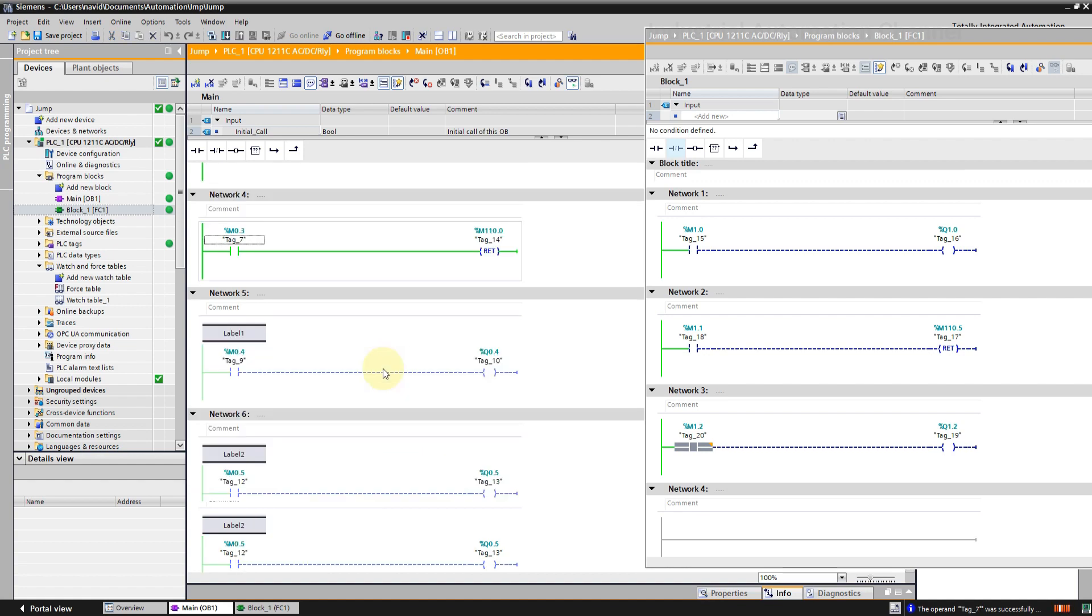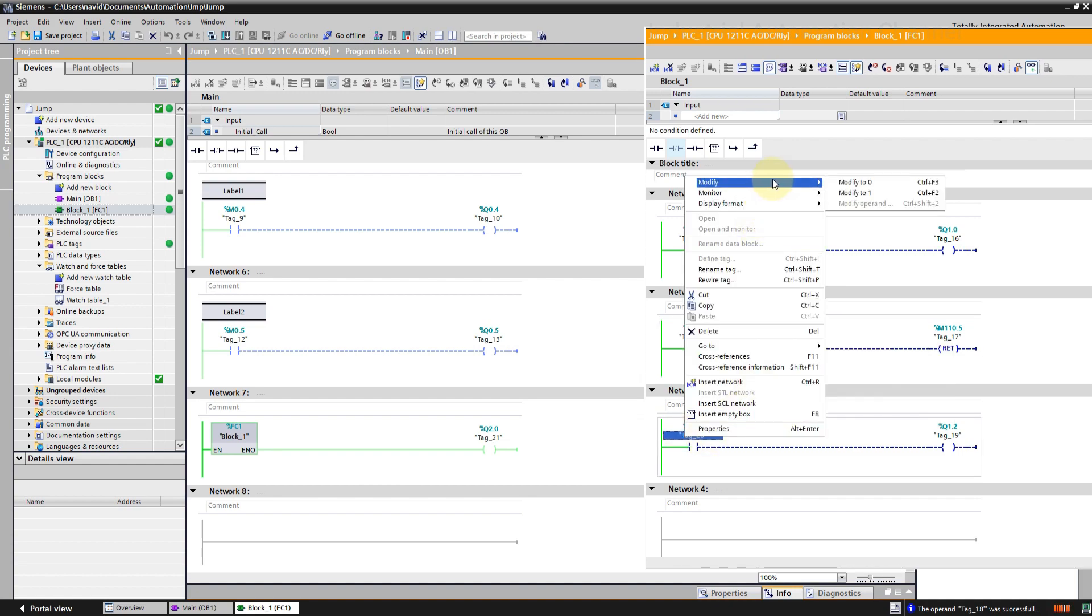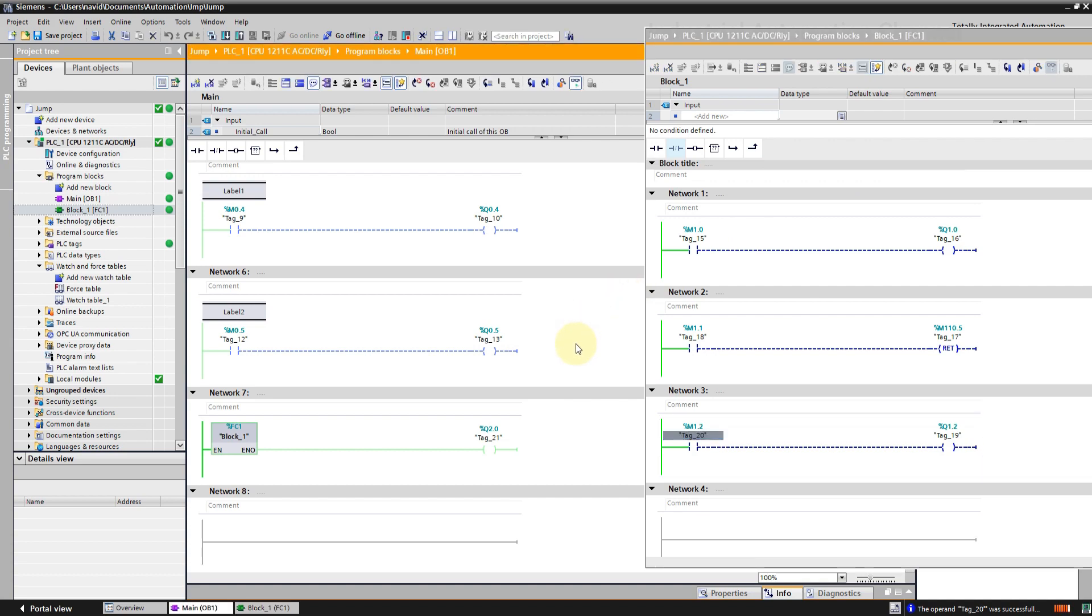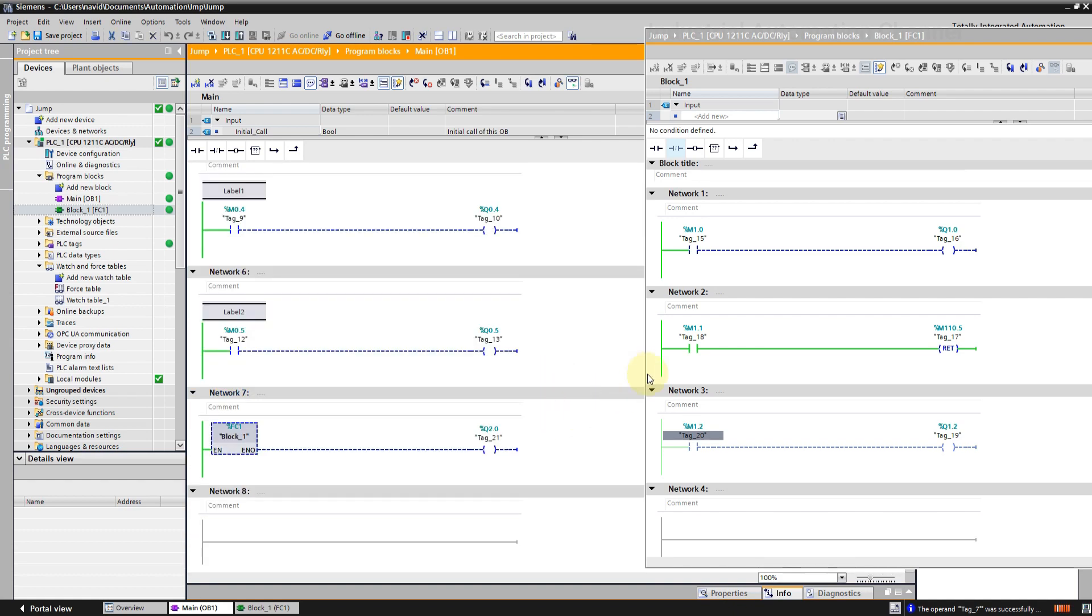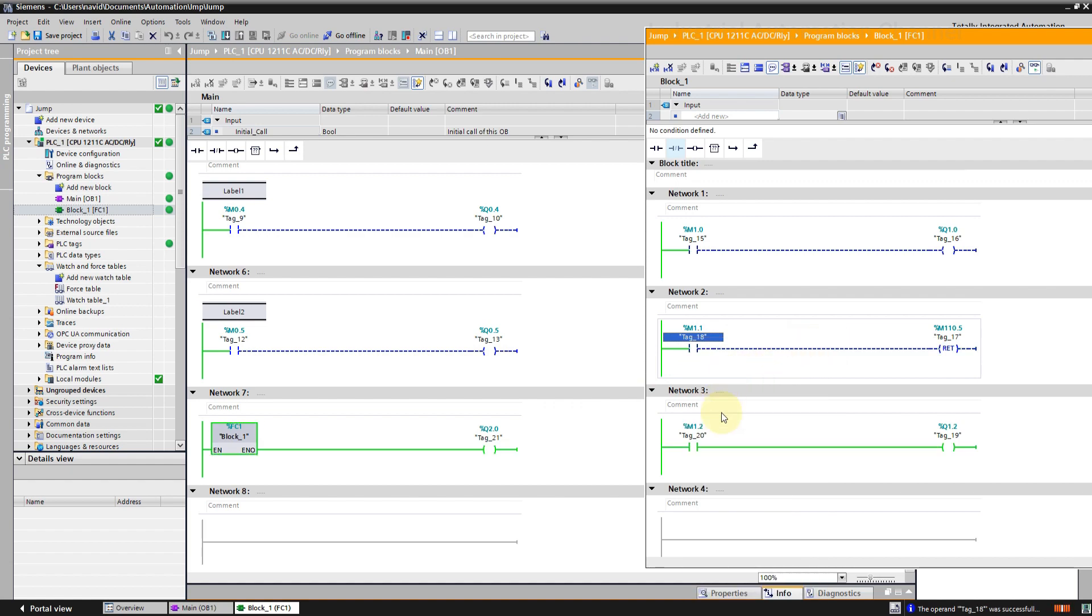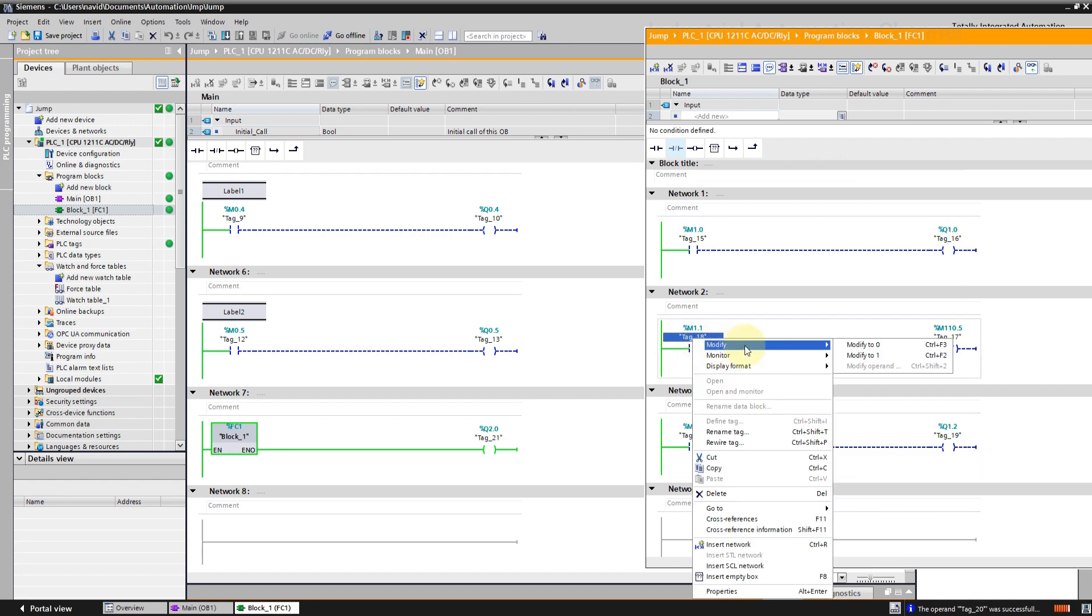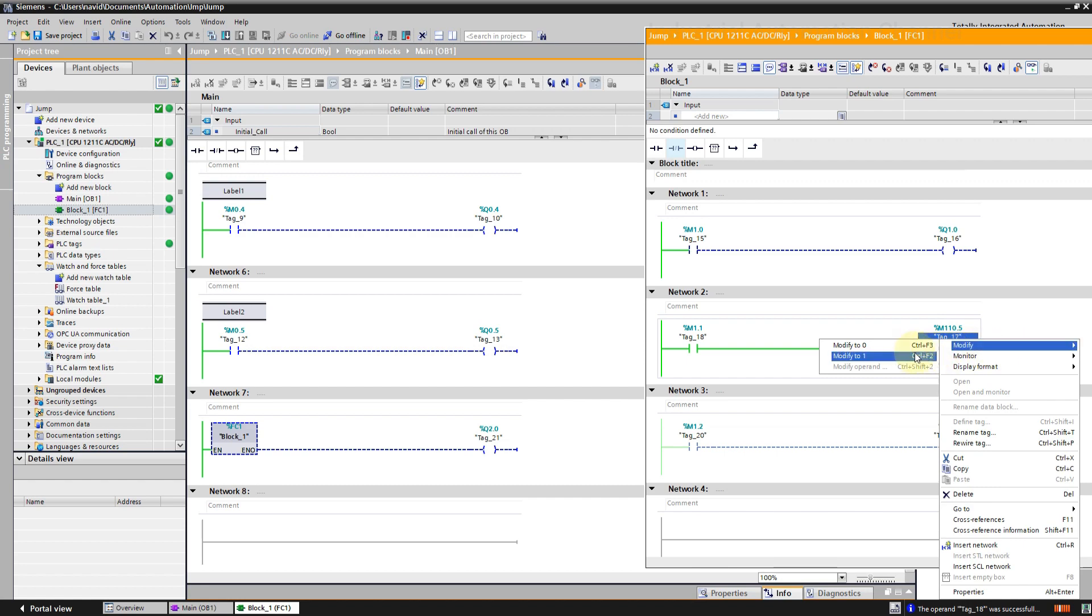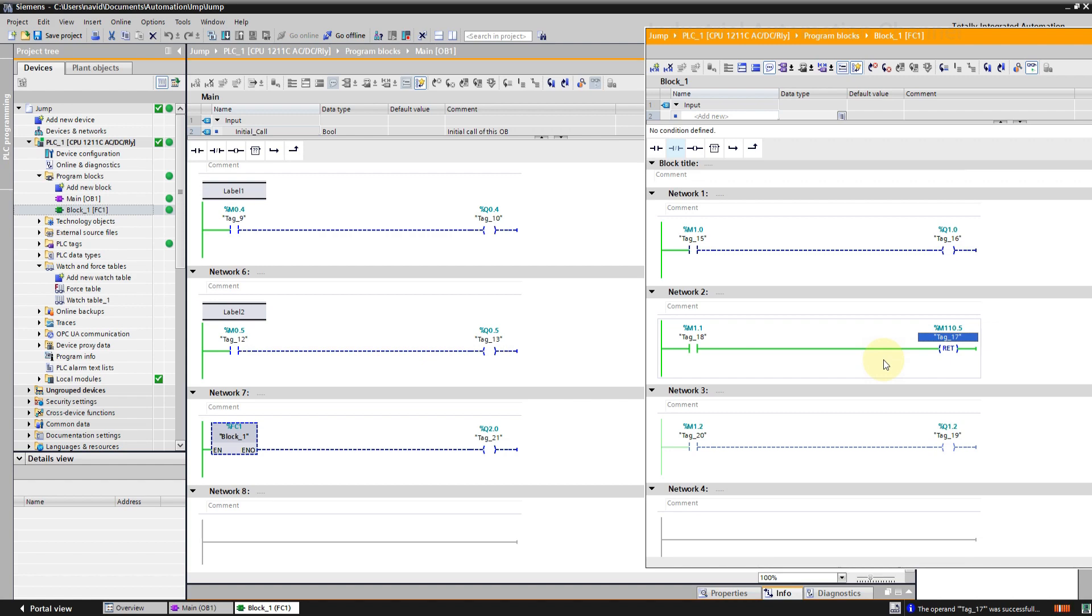I'm going to activate the first return inside OB. You see the networks under return are not scanned. Even FC is not working and when I change the variable nothing happens. Now let's activate this return inside FC, again the network under return is not scanned. Here we can change the return value of this FC. As you see enable output is now true. It can be used for example to say if the call of the FC was successful when the program execution reaches return instruction or not.